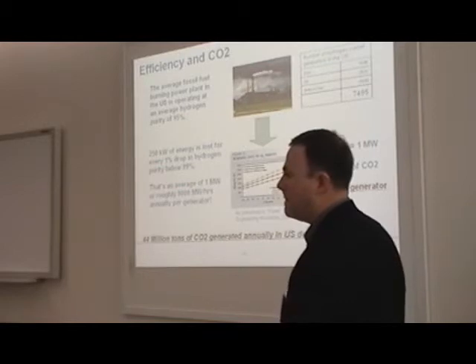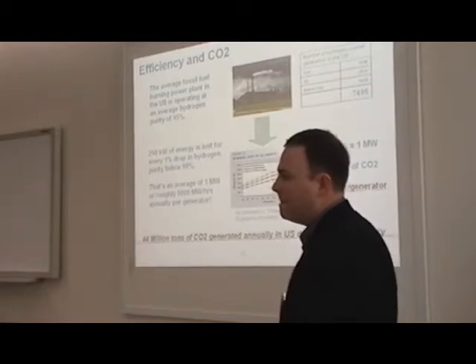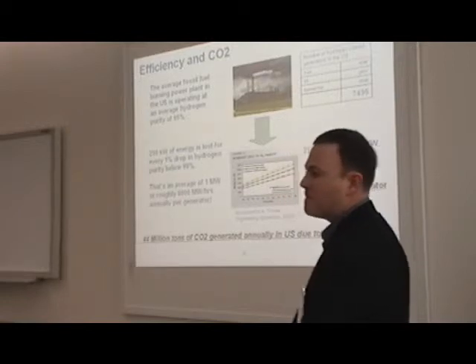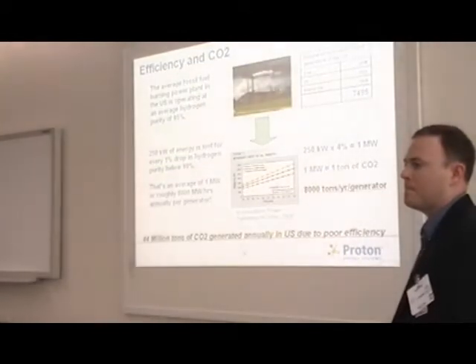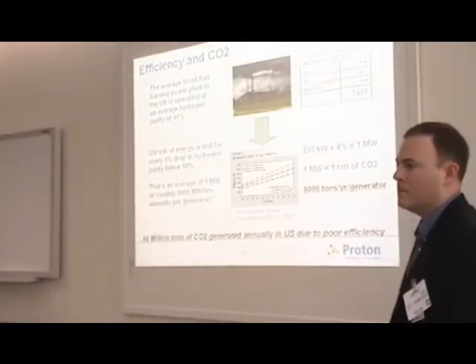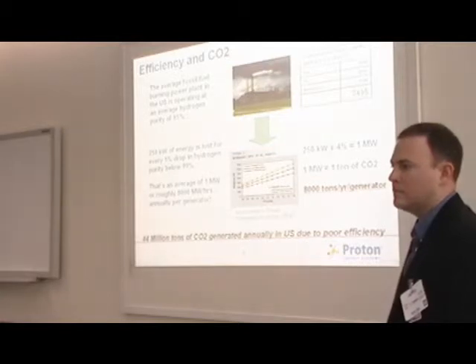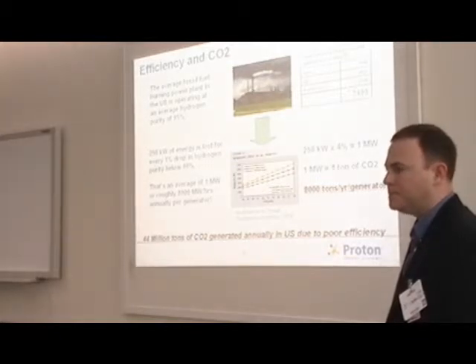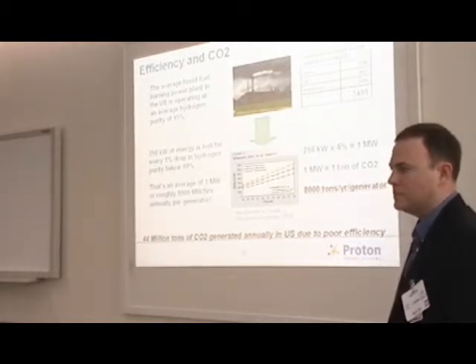One of the things you want to point out too, I think I'm correct in saying that a lot of your purity meters are the thermal conductivity type, where you've got a canister molecular sieve in front of the units. That 13X molecular sieve will take out water, CO2, any CO2 that's present, and turbine oil. The meter that's used on this system doesn't take out any of that. It isn't required. So you will actually get a more realistic reading with this system than you typically have in your generator.